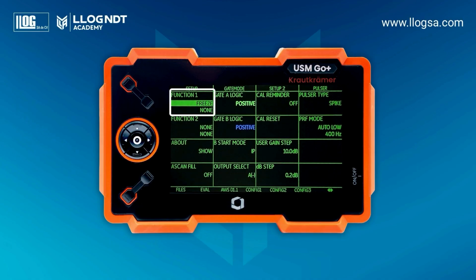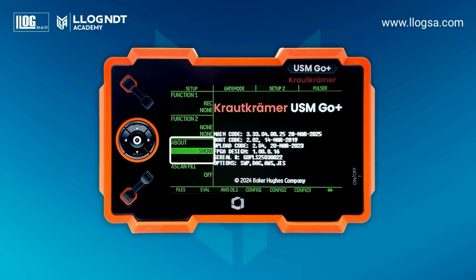Available quick functions include Freeze Display, Lock Joystick, Save Report or Screenshot, Auto Amplitude at 80%, Expand Gate, Decibel Step, Load a data set, Load calibration or parameters, Change display orientation, Enable envelope, Access the main menu, increase or decrease the refracted angle, and record video. All these functions can be assigned to function key 2. The next function displays information about the instrument.